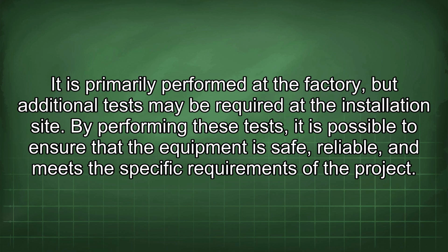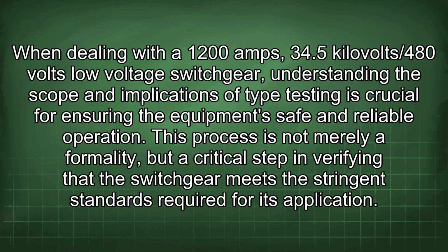By performing these tests, it is possible to ensure that the equipment is safe, reliable, and meets the specific requirements of the project. When dealing with a 1200 amps, 34.5 kV/480 volts low voltage switchgear, understanding the scope and implications of type testing is crucial for ensuring the equipment's safe and reliable operation. This process is not merely a formality, but a critical step in verifying that the switchgear meets the stringent standards required for its application.